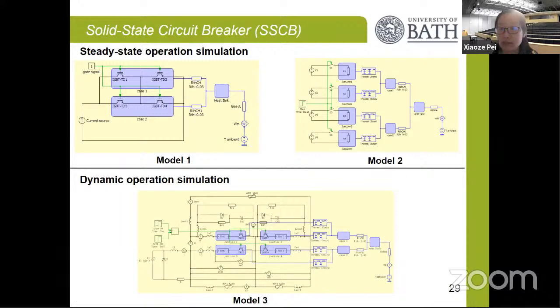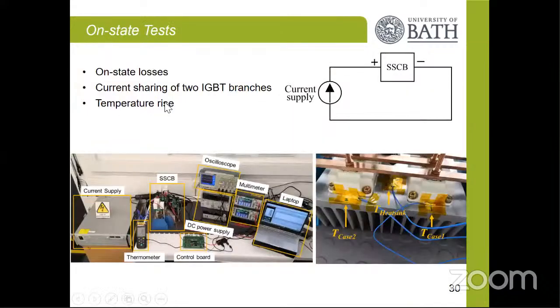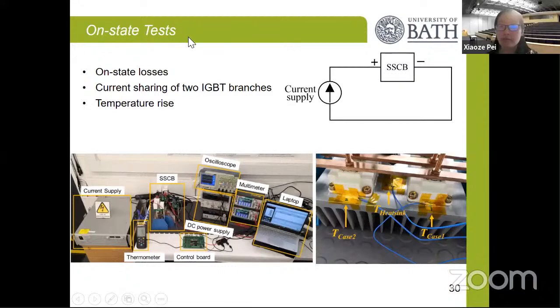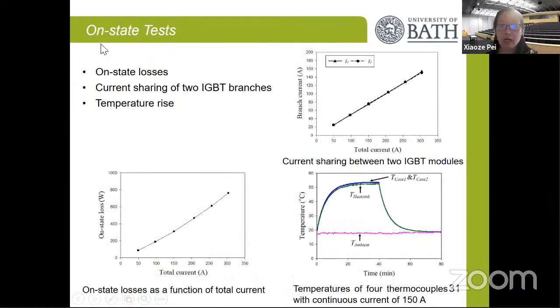In order to understand the behavior, we have some models for the steady state operation and the dynamic operation. In the lab, we set up an on-state, steady state test, investigating the solid state circuit breaker on its own, putting thermocouples on to measure the temperature rise at different current levels. At the steady state, we can see the current sharing in those 2 IGBTs is very balanced, which means those 2 IGBTs have a very balanced thermal behavior as well.